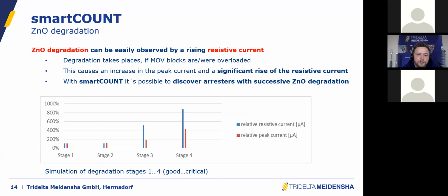Those values have been taken with the smartCOUNT on a surge arrestor which has been degraded step by step. That's why we see here stage 1, 2, 3, 4. We could say stage 1 is a healthy surge arrestor, normal condition, and stage 4 is a heavily degraded surge arrestor. You see that the relative increase of the peak current is much lower than the relative increase of the resistive current. Resistive current between stage 1 and stage 4 degradation is rising by almost 900% of its initial value. So this is a very clear indication that the surge arrestor is slowly degrading. With the resistive current, the power dissipation inside the surge arrestor is rising. Of course, it will get hot, and you will quickly run into a thermal runaway. And this has to be discovered before, of course. But we are capable of doing that.